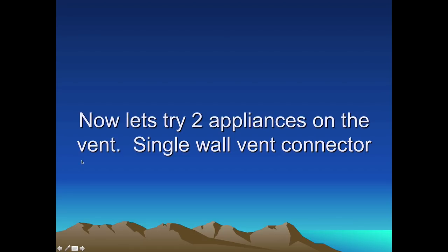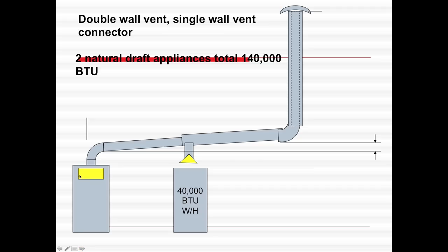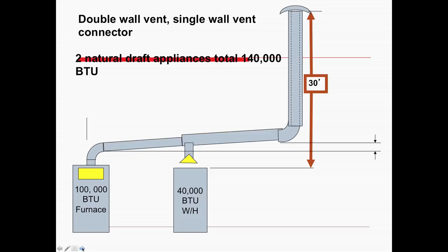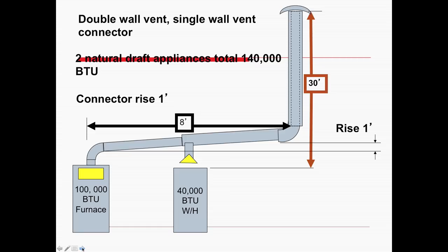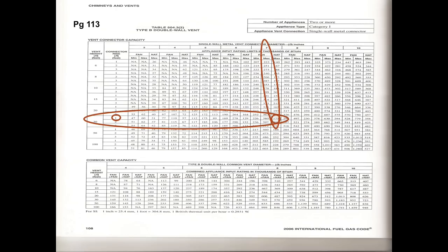Now we're going to try two appliances on the vent, using single wall vent connector again. Both of these appliances are natural draft appliances — two natural draft appliances totaling 140,000 BTUs: a 100,000 BTU furnace and a 40,000 BTU water heater. We have an eight-foot lateral, 30-foot height. The connector rise is one foot. We need to have at least one-quarter inch per foot on the rise. At 30-foot height with one-foot rise.